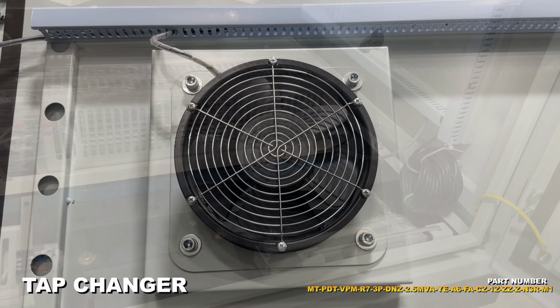This transformer is equipped with a 5-position tap changer to allow for small changes in voltage. This system has copper windings for high strength and electrical conductivity. This transformer features minimized air gaps and voids in the insulation, leading to increased durability and thermal stability.